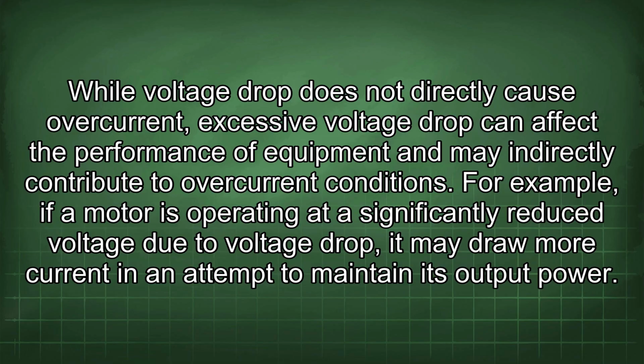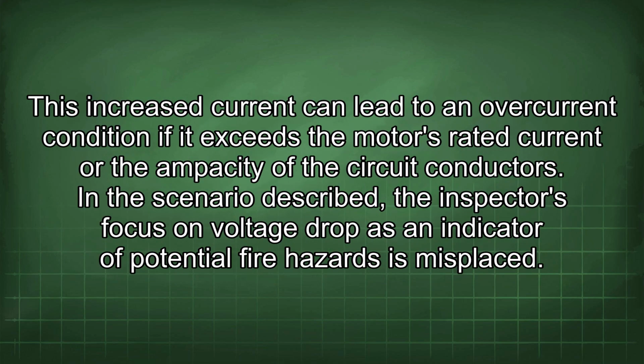For example, if a motor is operating at a significantly reduced voltage due to voltage drop, it may draw more current in an attempt to maintain its output power. This increased current can lead to an overcurrent condition if it exceeds the motor's rated current or the ampacity of the circuit conductors. In the scenario described, the inspector's focus on voltage drop as an indicator of potential fire hazards is misplaced.